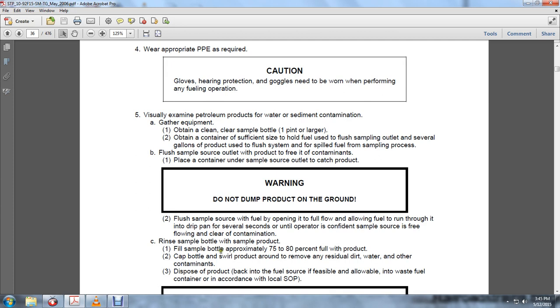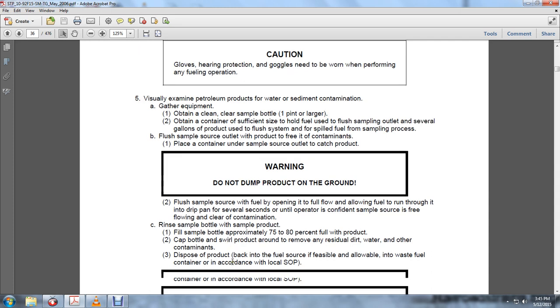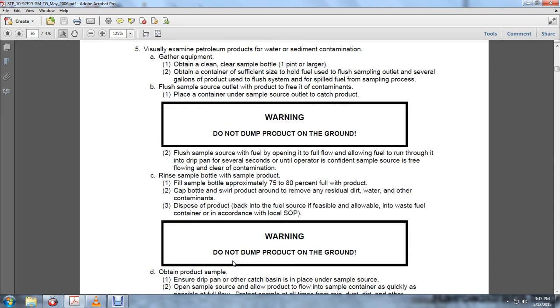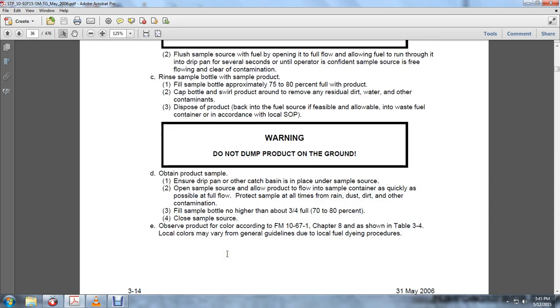Rinse the sample bottle with the sample product. Fill the bottle with approximately 75-80% of the product. Cap the bottle and swirl it around to remove the residue of dirt, water, and other contaminants. Dispose of the product back into the fuel source if feasible and allowable, or dispose of the waste fuel in accordance with the local SOP, standard operating procedures. Warning: do not dump product on the ground.